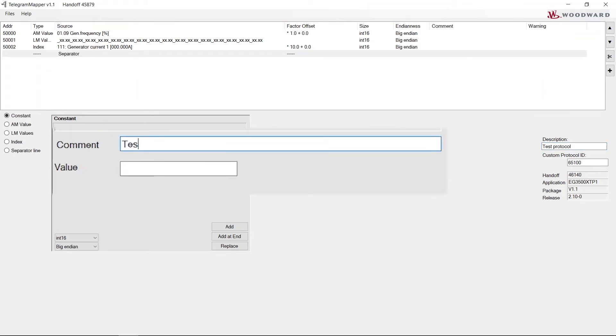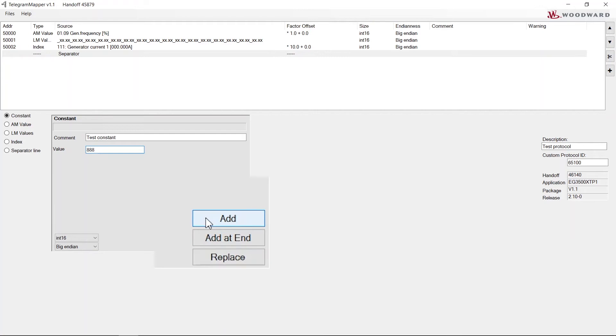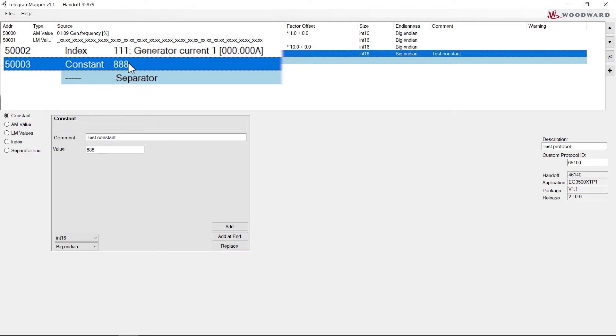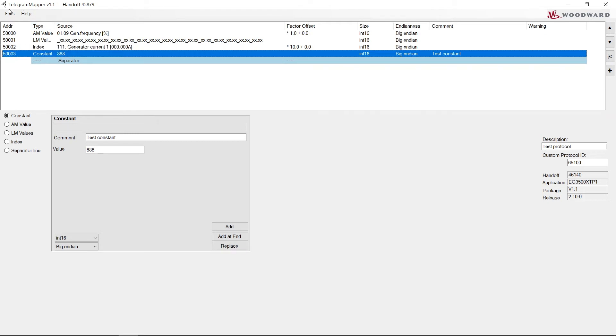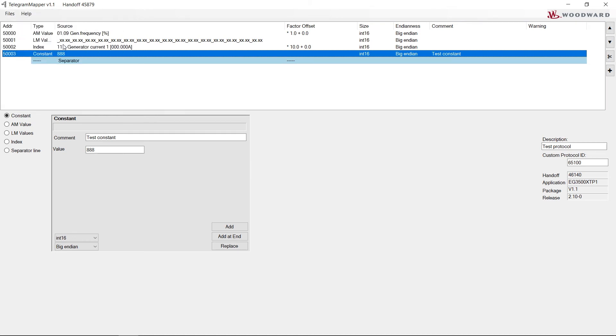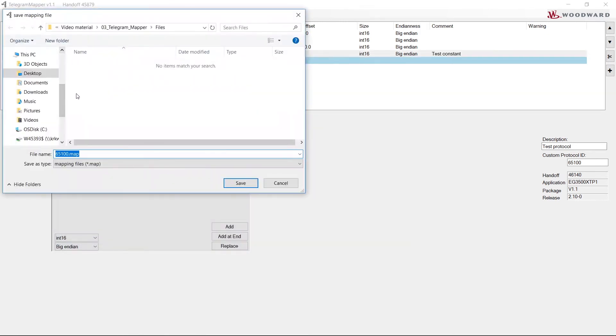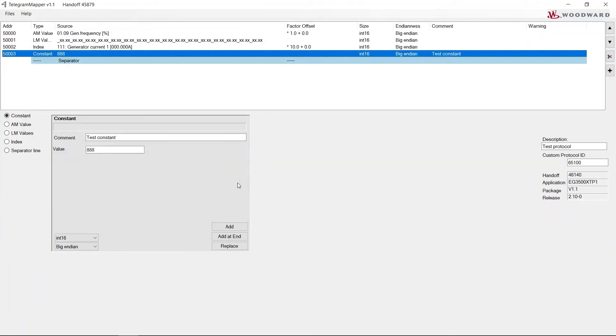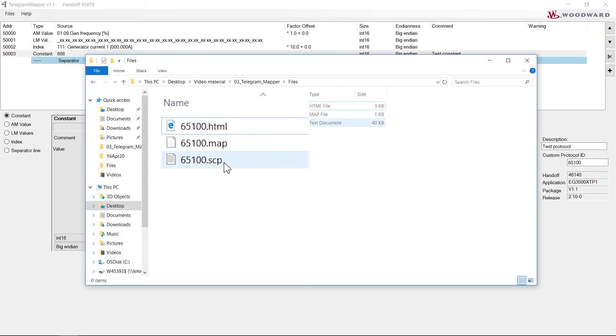Now we create a test value which we later read from our EasyGen XT unit. The constant will be, for example, 888. Let's note the address at which we created the 888 value. After entering your custom data points, you can create SCP, HTML, and MAP files with the Create Mapping Files option.